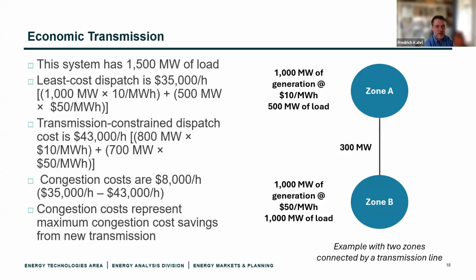Notice that our costs have gone up because we have to dispatch more generation in zone B due to transmission constraints. So in this example, our congestion costs are going to be $8,000 per hour. You can think about this as the max. If we were to build new transmission, this is the maximum amount, at least in this hour, that we could save in congestion costs. This would be our maximum congestion cost savings from building new transmission.